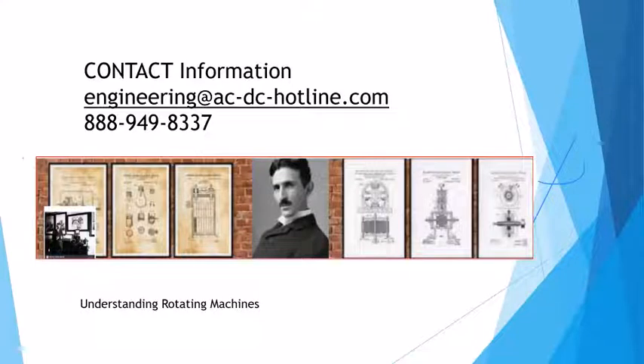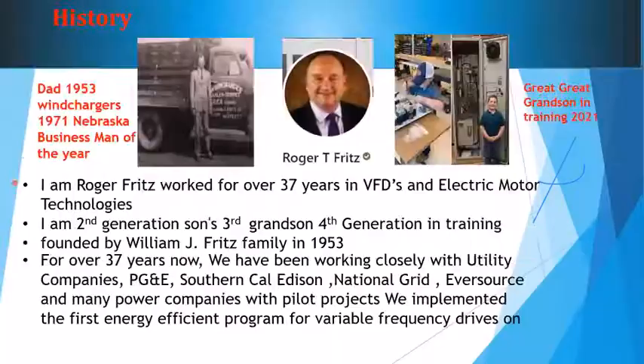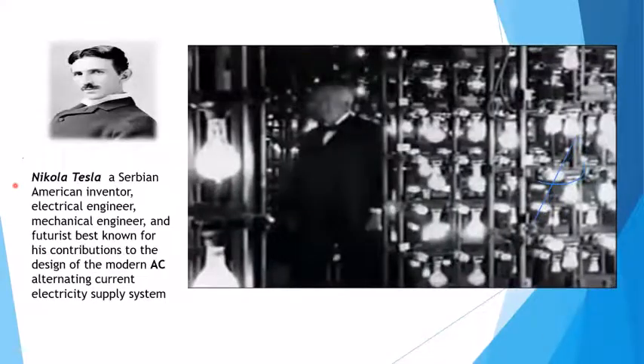Mr. Fritz, I know this is verboten in the drive manufacturer's literature, but I've seen plenty of times where they've run the incoming power and the motor conductors together over a significant length. I know that's not good, but can you explain why that's not good? Well, it's not good because, let me go to the drawing.